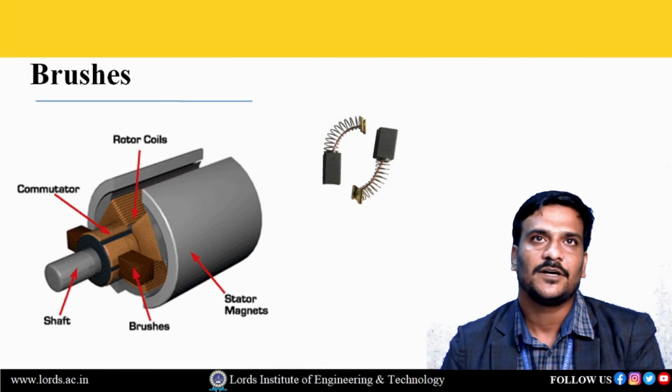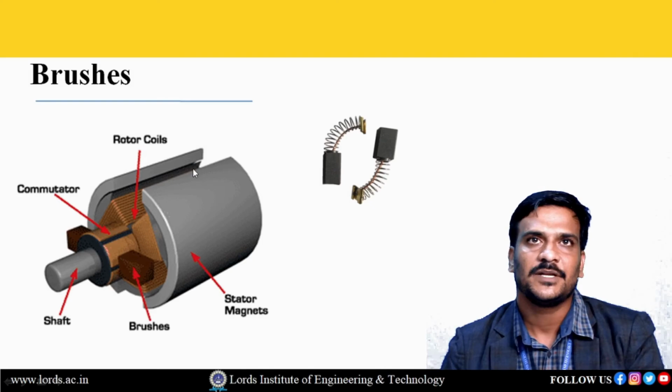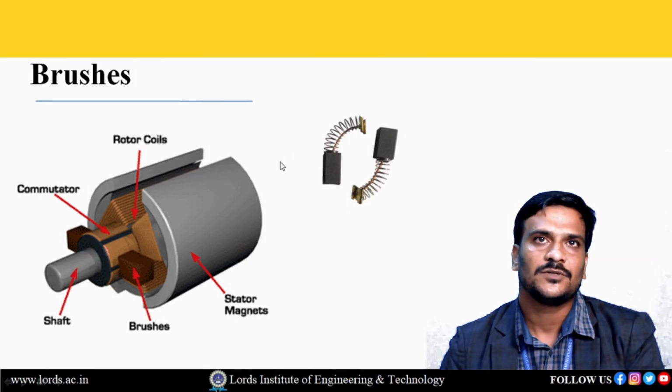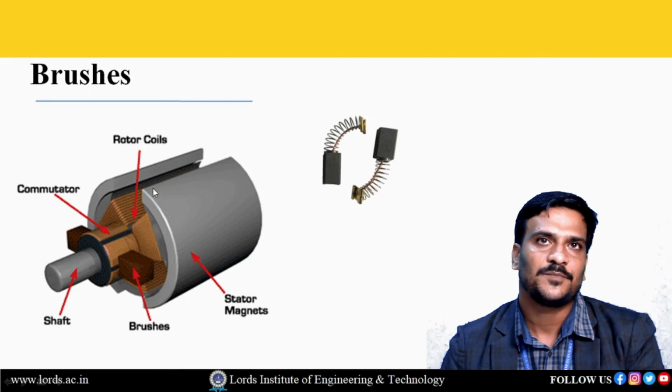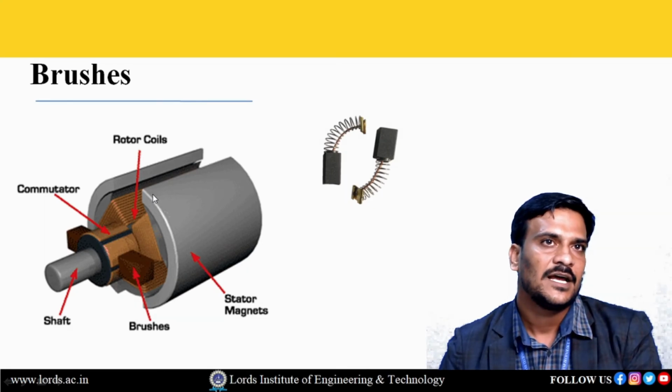Another important part is the springs, which keep brush pressure towards the commutator. We have to take care in maintaining this pressure. If excess pressure is applied, it may lead to wear of the brushes, and if less pressure is applied, it may lead to excessive arcing at the contact between the commutator and the brushes. So this is how brushes are.